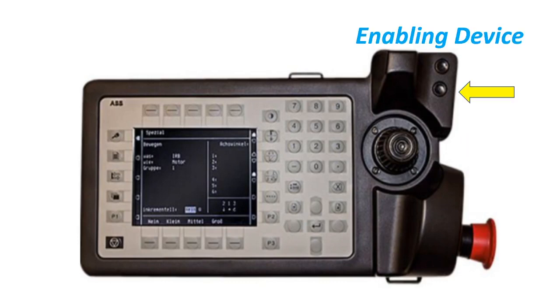Enabling Device for Safe Operation: when the enabling device is released or pushed all the way in, the guard stop will be activated, meaning the motor is off. To activate the enabling device, press it halfway and the motor will turn on.